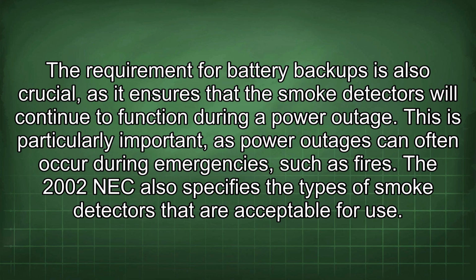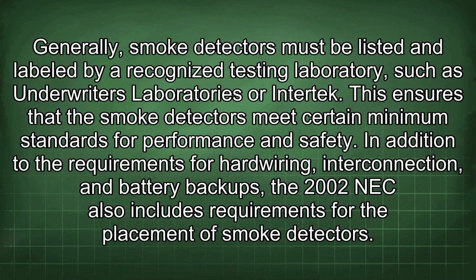The requirement for battery backups is also crucial, as it ensures that the smoke detectors will continue to function during a power outage. This is particularly important, as power outages can often occur during emergencies, such as fires. The 2002 NEC also specifies the types of smoke detectors that are acceptable for use. Generally, smoke detectors must be listed and labeled by a recognized testing laboratory, such as Underwriters Laboratories or Intertek. This ensures that the smoke detectors meet certain minimum standards for performance and safety.